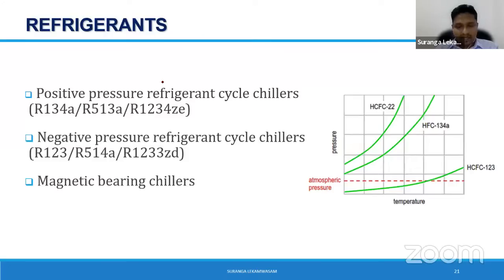Right? So we were talking about that in a very simple summary. Then I wanted to highlight the importance of refrigerant, right? Refrigerants are man-made substances. Simply, I can categorize the refrigerants into two streams. I am touching on the chillers, right? In chilled water applications, you can find chillers with positive pressure refrigerant and negative pressure refrigerant.